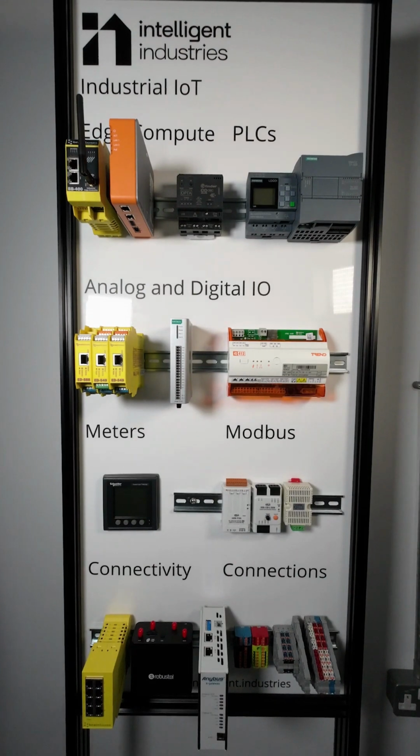Okay, so let's move on to talking about inputs and outputs. Inputs and outputs typically come in two flavours. You have analog and you have digital. Digital inputs are where a signal is either on or off, and analog signals are typically where a signal is between a range. So for example, with 0 to 10 volts, you could have a signal that's 5 volts and we can measure that. Or you can have a current signal, for example, where it might be 4 to 20 milliamps, and we're measuring the current between those two known points.